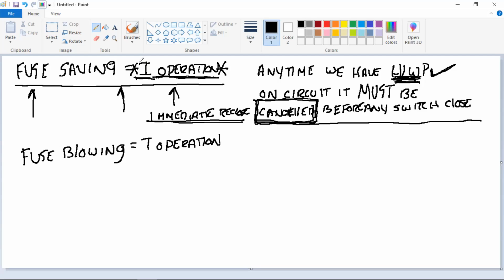Okay, I'm tracking. The I operation in normal day-to-day, when I don't have a hotline work permit, is meant for an I open, an immediate reclose, a fuse blow, and not go to timed. That's the way your system is designed. Of course, that's going to depend on the fault intensity and the size fuse you're working with, but that's the way you want your system to work. A real fast open close like that, hopefully customers don't even recognize it, the fuse blows, and then just one section of line is out rather than the whole feeder.